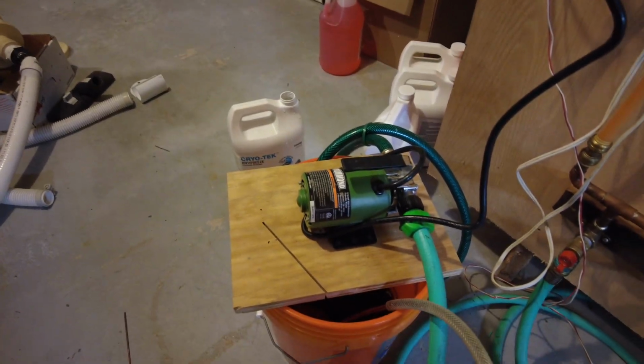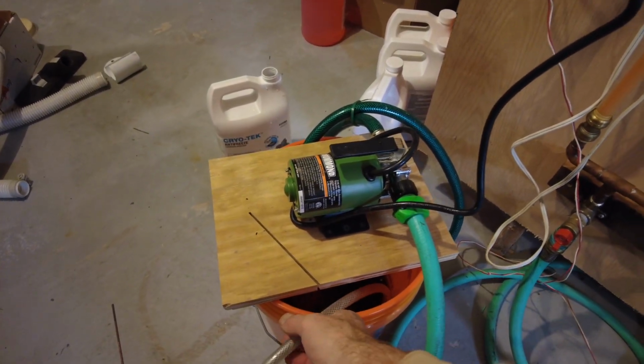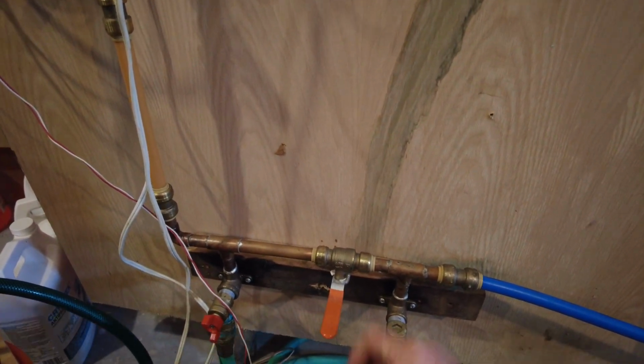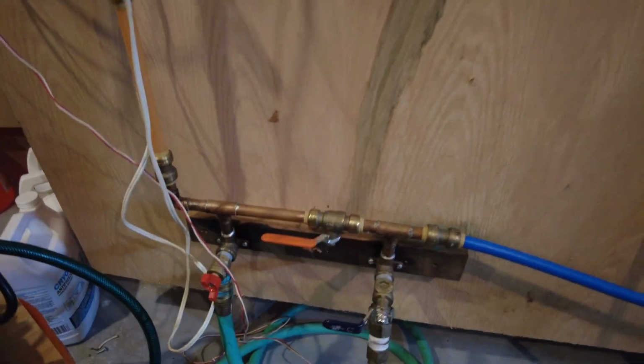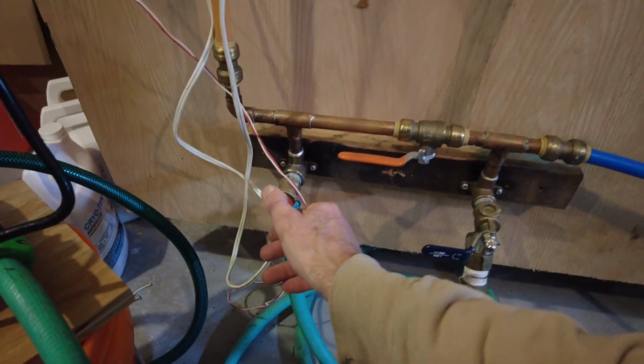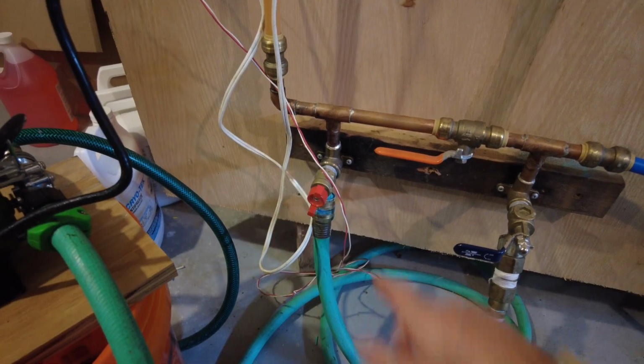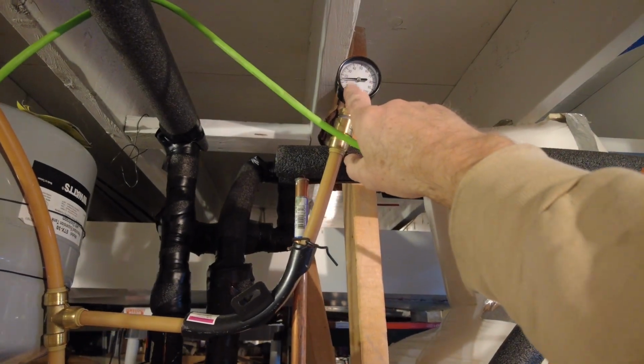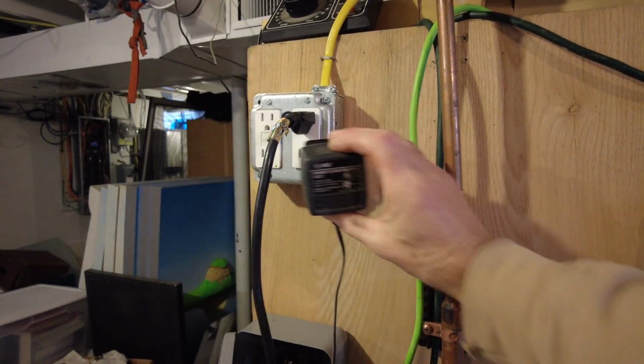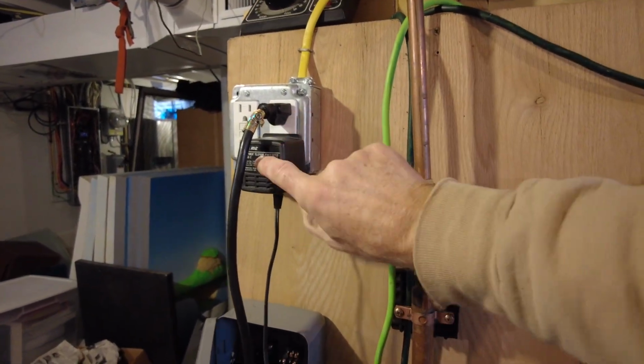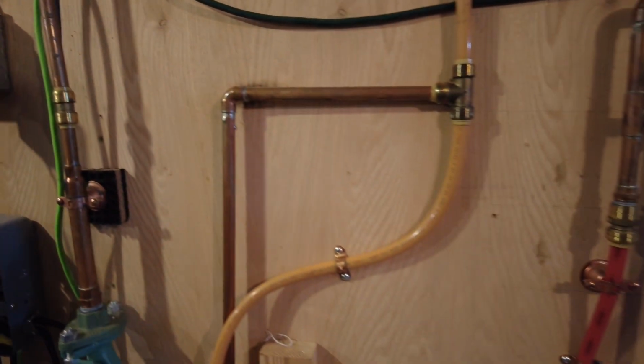Once I'm convinced I've got good circulation, I'm going to shut this off, open this up, and then close this, which closes off the pump, and then unplug the pump. Come up here, check my pressure, which is good. Now, instead of overriding it, I'm going to plug that back in, and these won't come on.